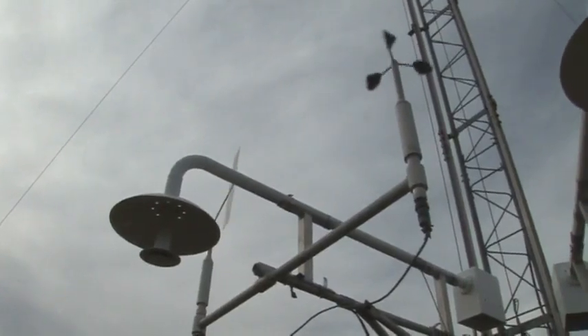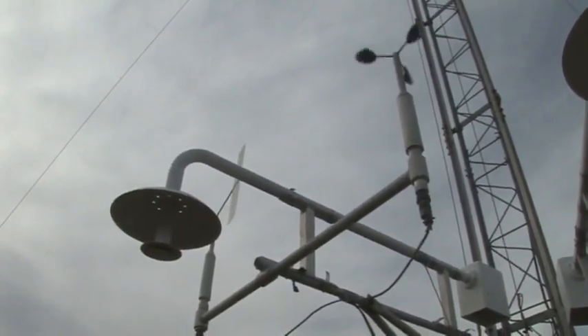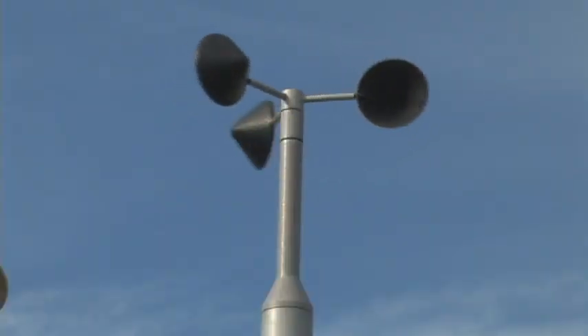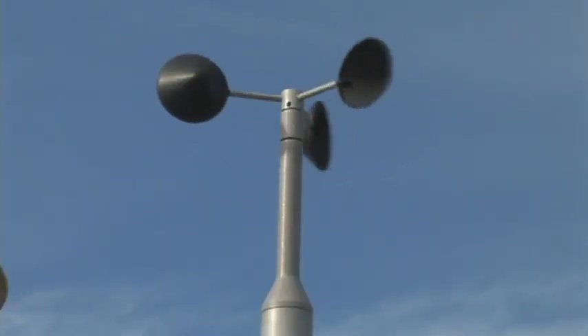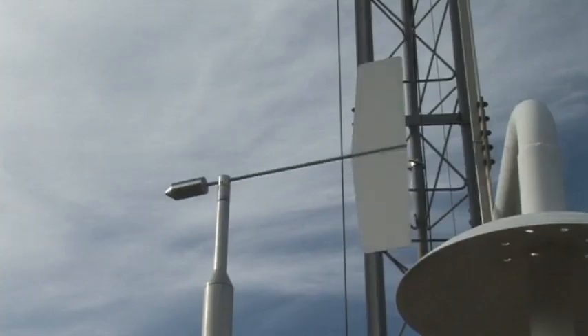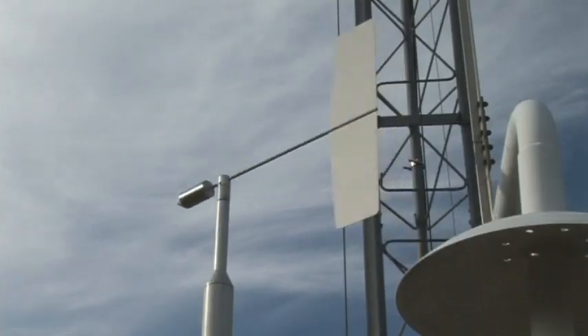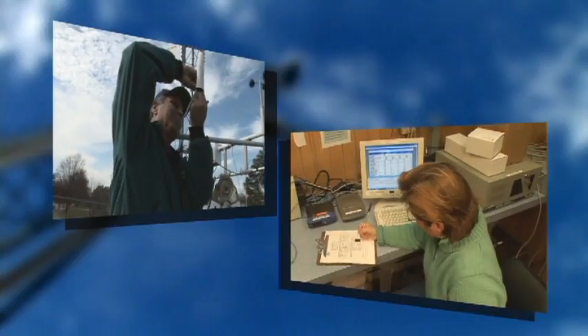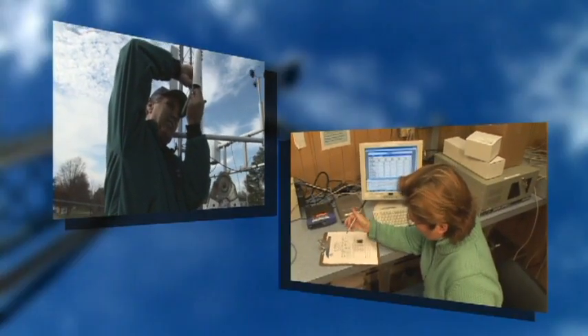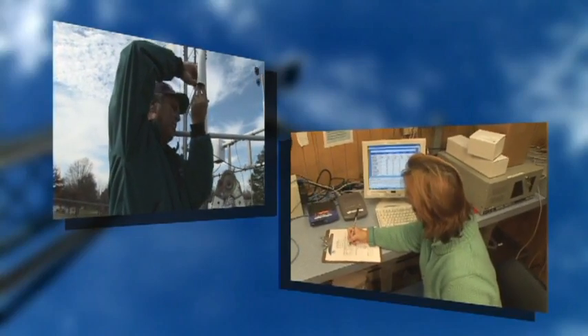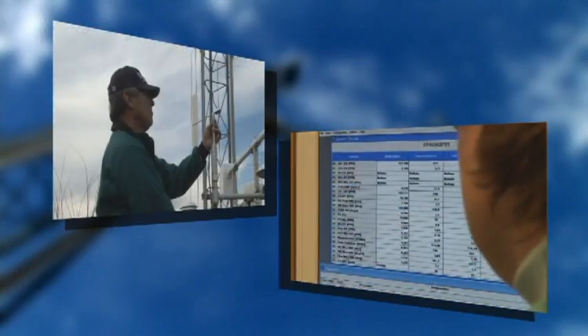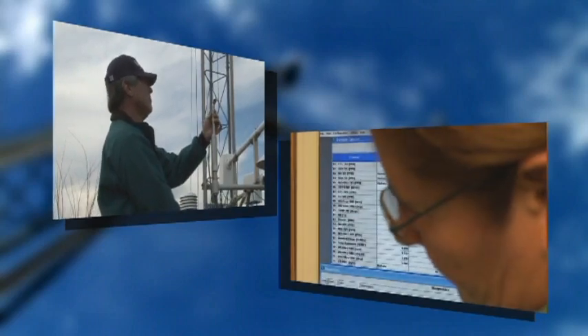For wind speed and wind direction sensors, this means imitating either wind speed or, in the case of the direction, the direction from which the wind is blowing. The wind speed calibration is performed by spinning the anemometer sensor at a particular rate of speed, or revolutions per minute, also known as RPMs. The wind direction is calibrated by referencing a particular direction as a reference point. Calibrations of meteorological systems always take at least two people to perform. The reason is simple. While one person is performing the test on the instrument, another person must record the responses.